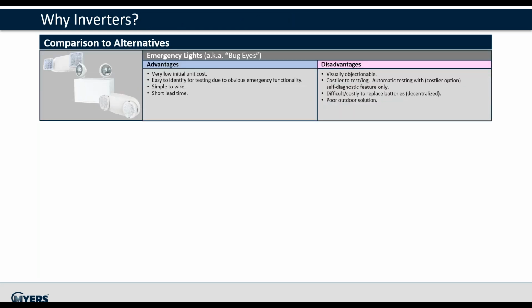Summarizing the advantages and disadvantages of the different types of emergency lighting solutions, starting with the unit equipment, on the plus side: very low cost, simple to wire, readily available, and easy to identify the emergency fixtures. Disadvantages are that it is objectionable to most people in spaces, costlier to maintain, testing and logging, and if it has auto test self-diagnostic units, there's a higher per fixture added cost, and it's a poor outdoor solution.